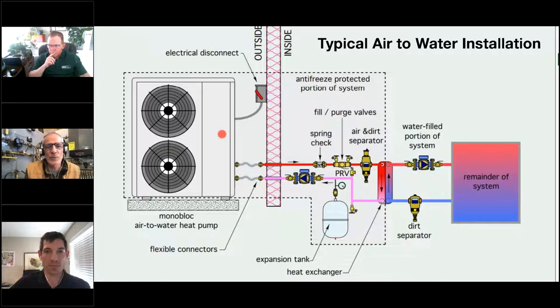That picture actually shows what looks like a combination air and dirt separator on the top. And then we've got another dirt separator on the other side where we've got the flat plate heat exchanger. So we've got two different fluids working here. We've got the flat plate heat exchanger. That's a separate system with its own pump, its own separator, and would have an expansion tank too. So what else can I talk about there? Expansion tank sized properly, of course.